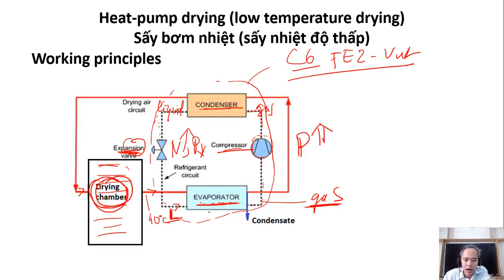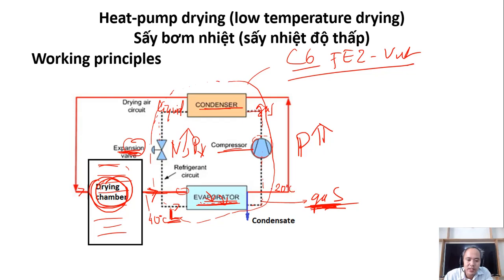In the evaporator, the liquid is converted into gas — this process is endothermic, meaning it absorbs energy; it needs energy to evaporate. We introduce the output air from the drying chamber to exchange heat with the evaporating refrigerant. The refrigerant takes energy from the output air to evaporate, so the temperature of the output air can drop down to maybe 20°C or 15°C, depending on the design.